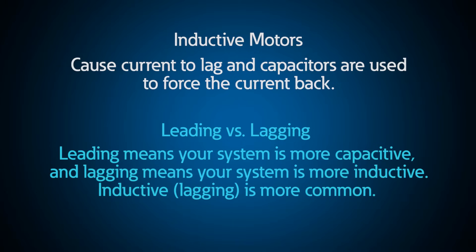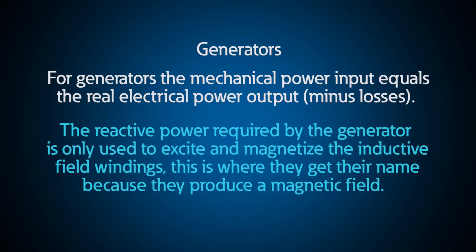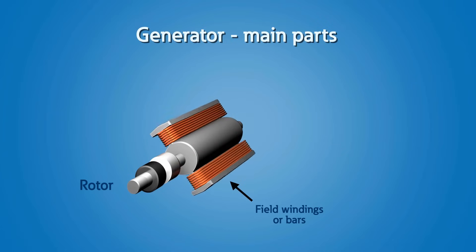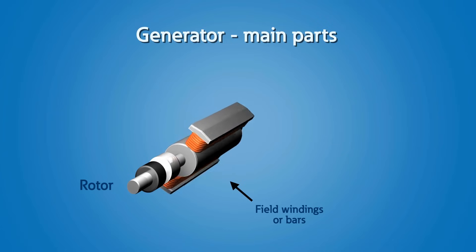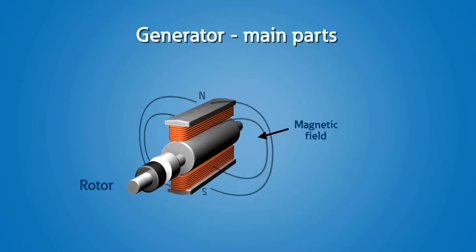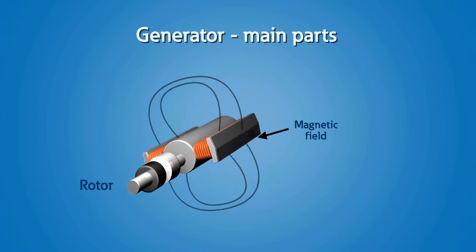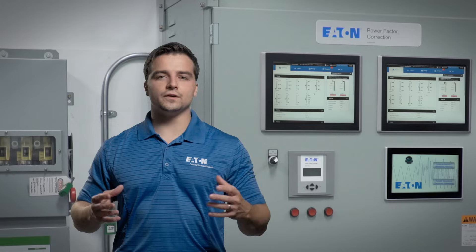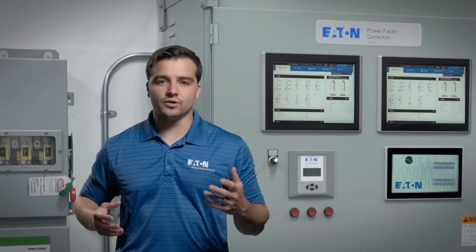Leading means your system is more capacitive, and lagging means your system is more inductive, which is more common. For generators, the mechanical power input equals the real electrical power output. The reactive power required by the generator is only used to excite and magnetize the inductive field windings — this is where they get their name because they produce a magnetic field. The resultant magnetic field isn't doing any real work.